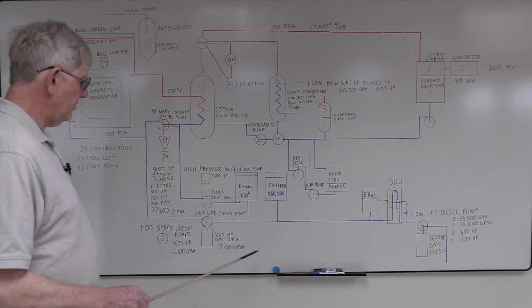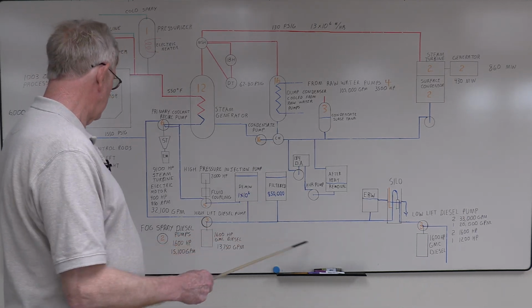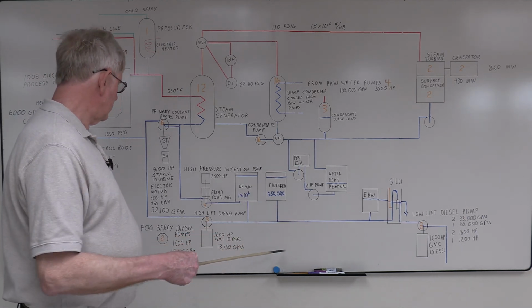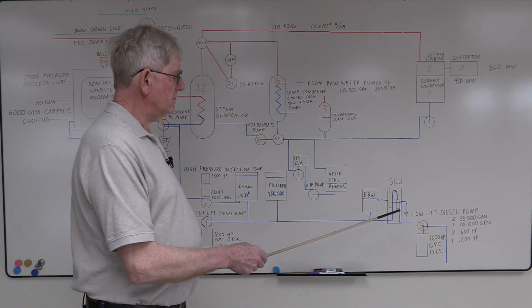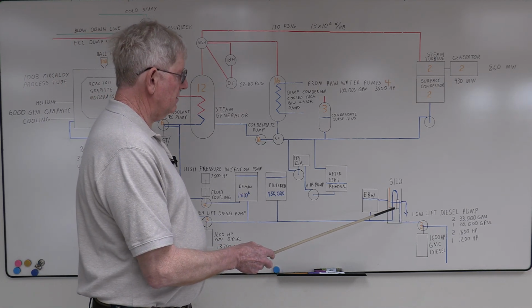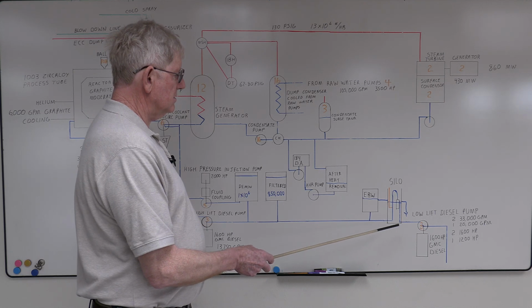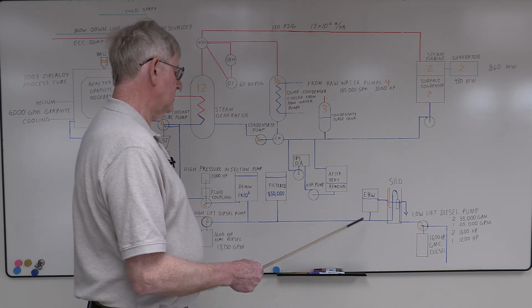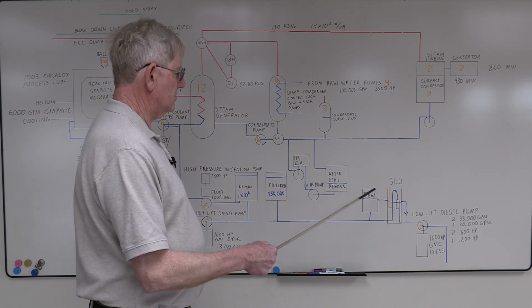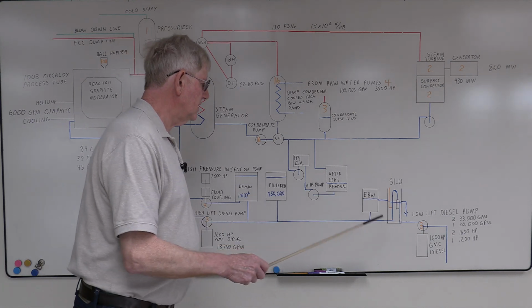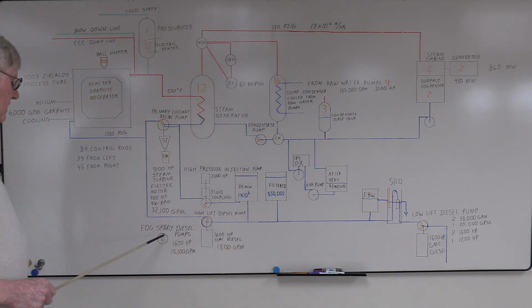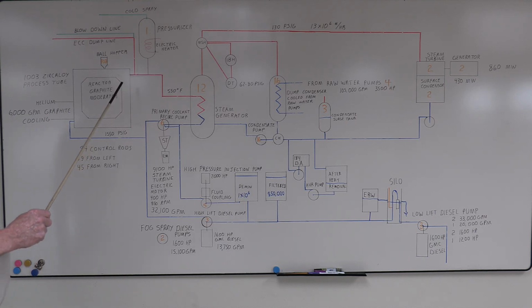These took water really off the emergency raw water tank. The purpose of this was to provide water to these pumps while your low lift pump started. They had to pump water up the hill a little ways, so it took a little over a minute to get water up to here, to your fog spray pump header. So this was kind of an interim tank that would provide water while those caught up. Fog sprays were for the pipe gallery in case there was a pipe rupture. They'd also provide emergency water to the graphite cooling and shield cooling.